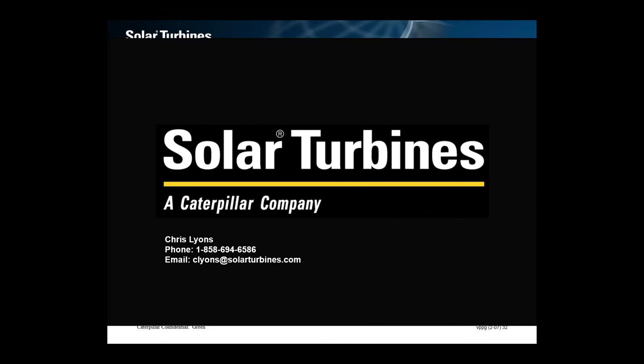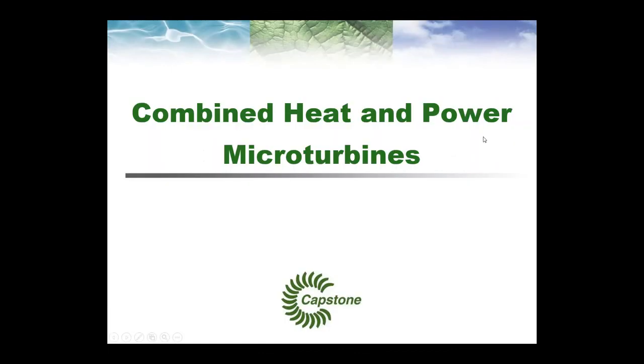We used to just deal with it and let it pass through, but we've since developed technologies, just the same way you would remove moisture. When you drop the water out and cool the gas, the siloxanes come with it. And then you also have other technologies like the gels that dry air. They use those types of technologies in a carbon filter with some chilling of the gas to knock the water and the siloxanes down. And that gets it to levels that allow us to operate the gas turbine.